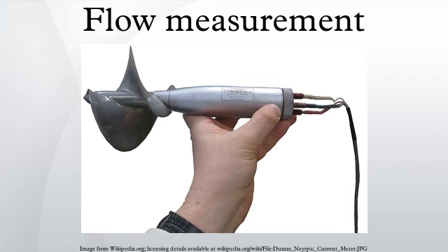The frequency is measured and the flow rate is calculated by the flowmeter electronics using the equation, where f is the frequency of the vortices, L is the characteristic length of the bluff body, V is the velocity of the flow over the bluff body, and St is the Strouhal number, which is essentially a constant for a given body shape within its operating limits.